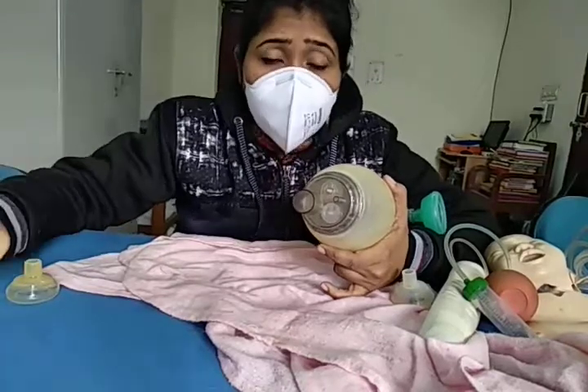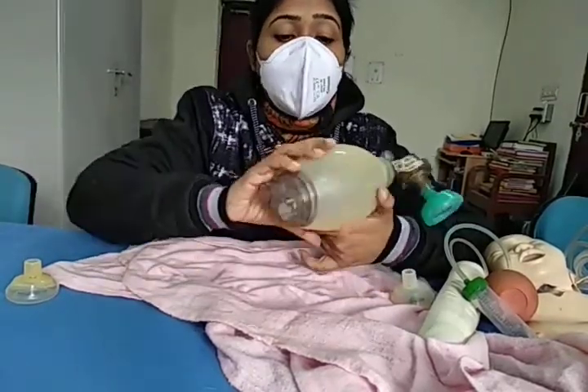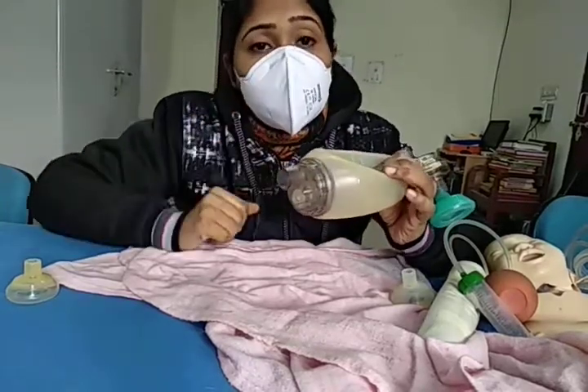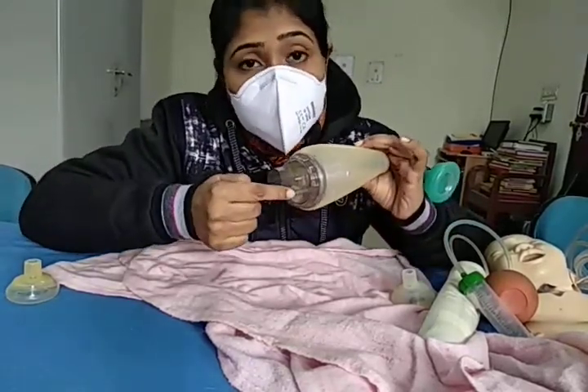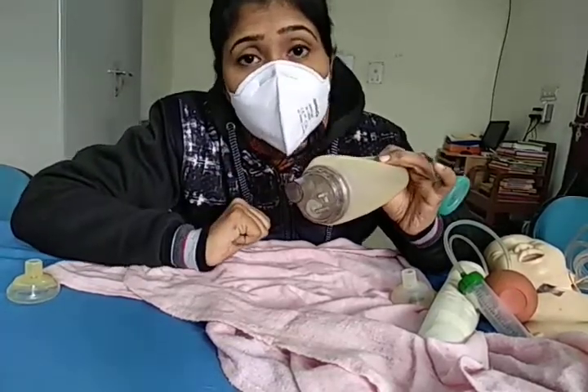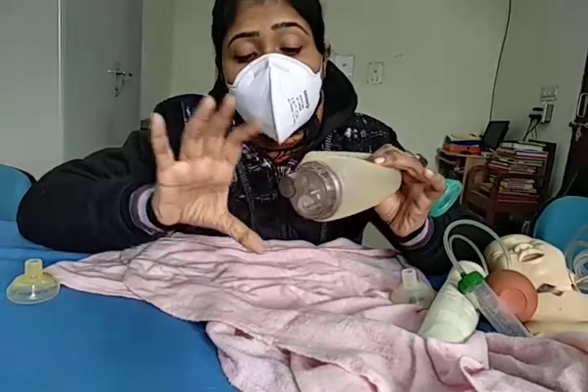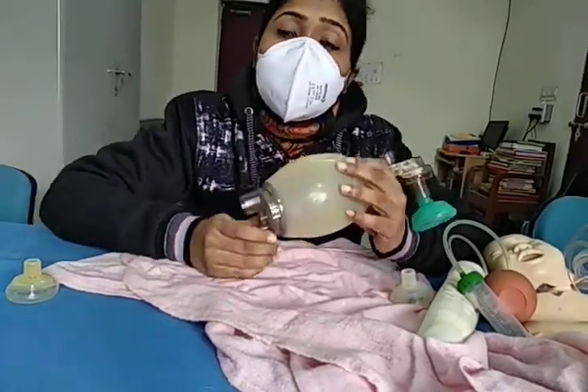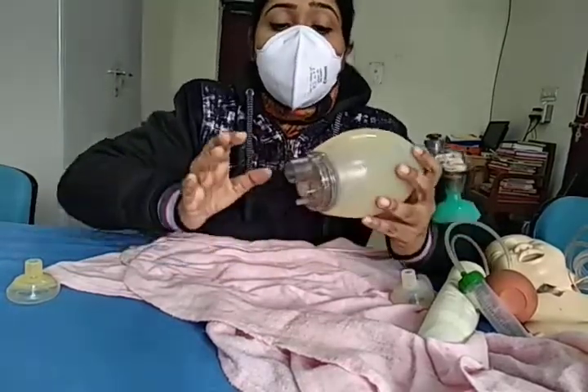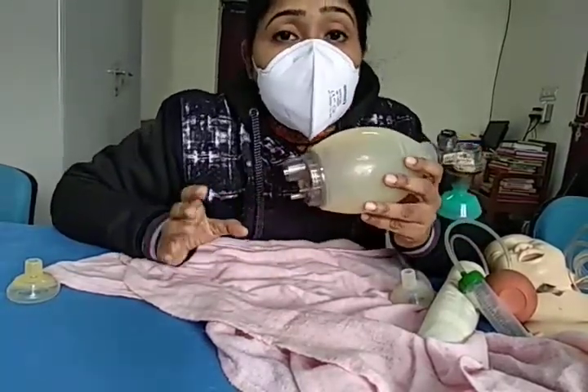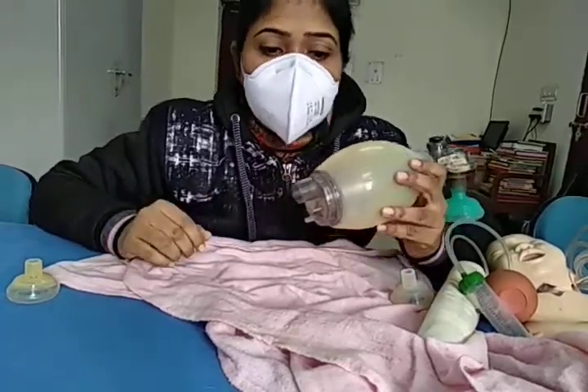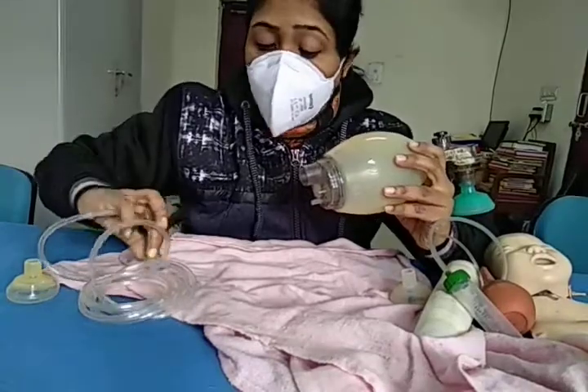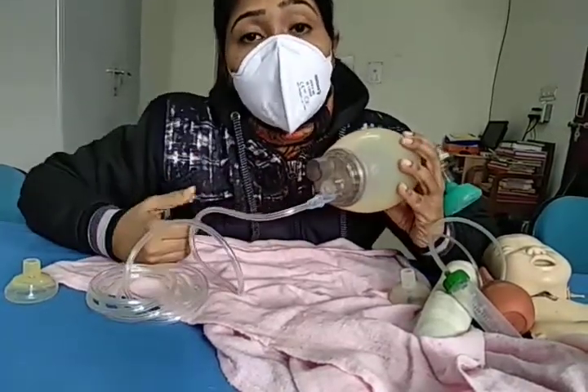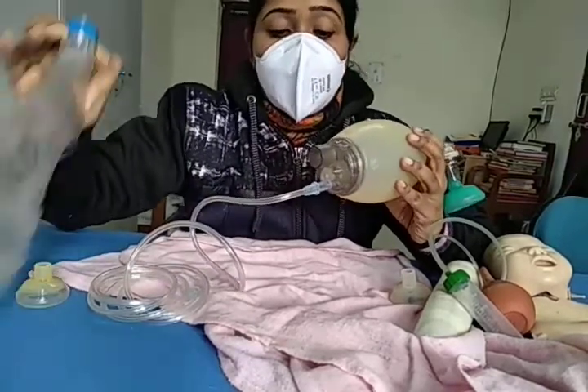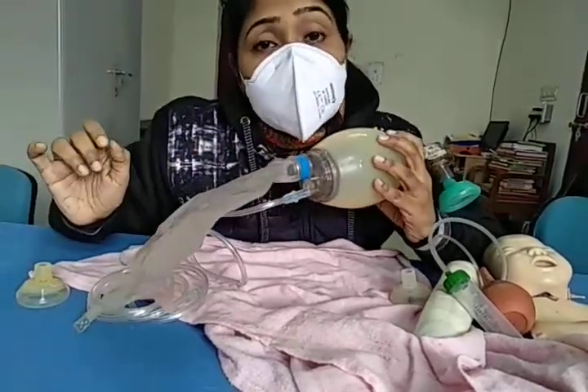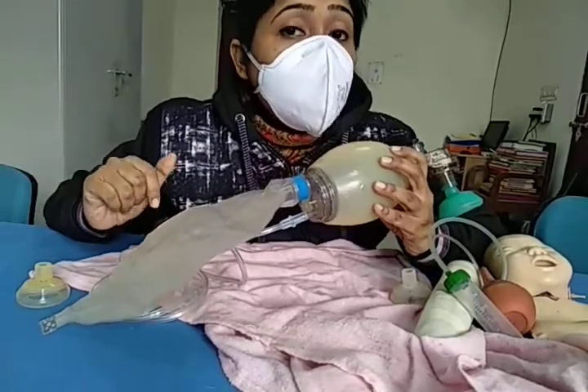Now, this is an empty bag. How is it filled up with oxygen? So, when we press the bag and the inlet valve is closed, then oxygen from the oxygen tube goes to the reservoir bag, and thus after a few compressions, the bag will be filled up with oxygen. Now, when we don't attach any tube, it will give 21% oxygen of air. When we only attach the oxygen tube here, it will give 40% oxygen. And when we attach the oxygen tube and oxygen reservoir both, then it will give 90 to 100% oxygen.